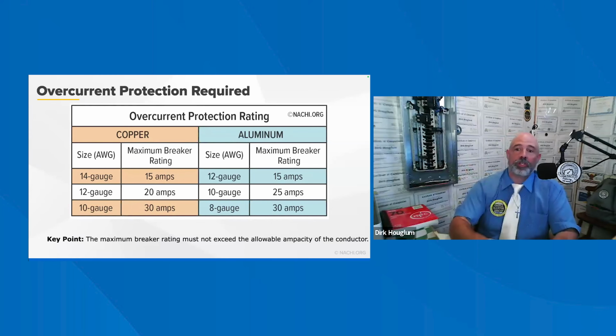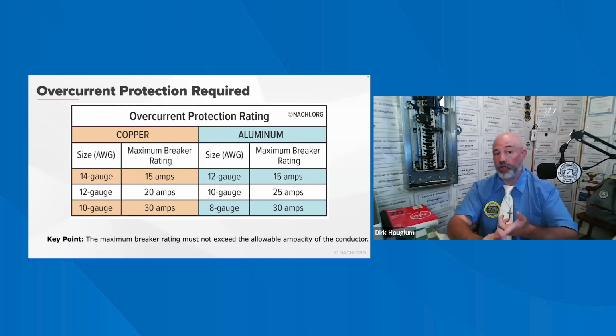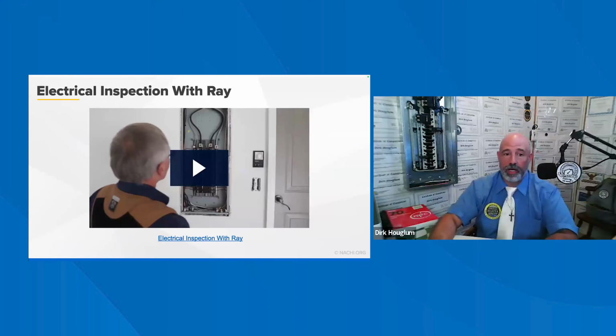For small conductors, commonly seen by home inspectors in residential buildings, the rating of the breaker must not exceed the rating of the conductors or the wires. So the key point here is the maximum breaker rating must not exceed the allowable ampacity of that conductor. So keep an eye on it: you're using 14 gauge for 15 amps, 12 gauge if it's aluminum. So kind of keep that in thought. And here is a video.